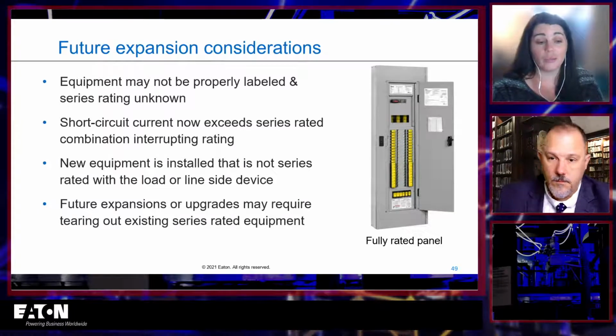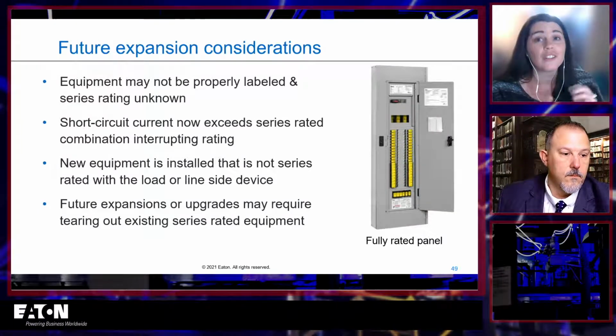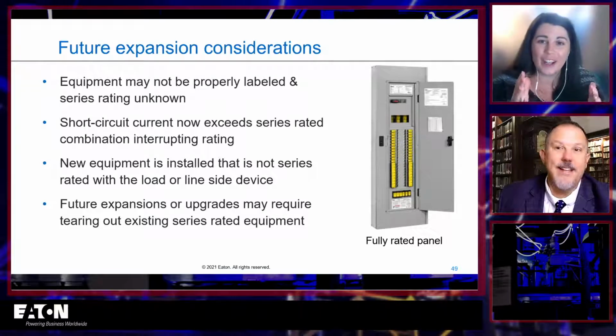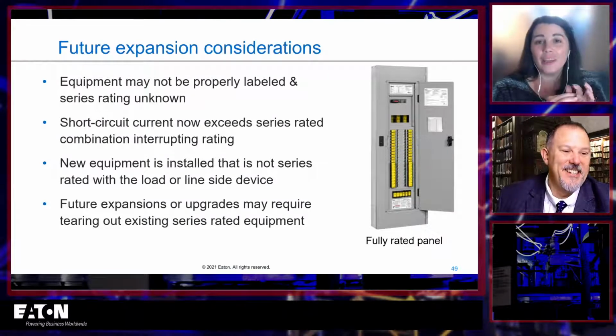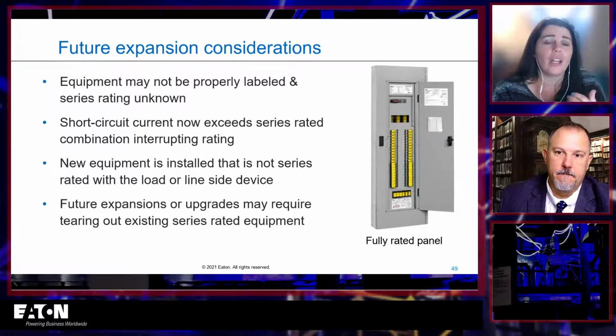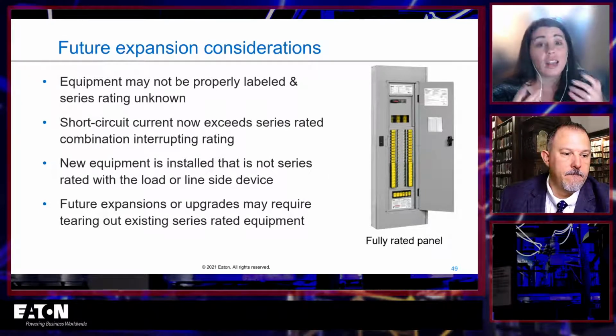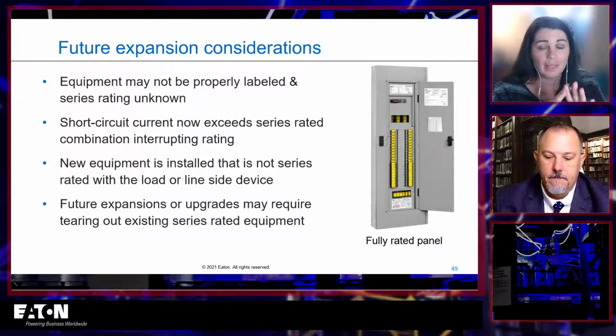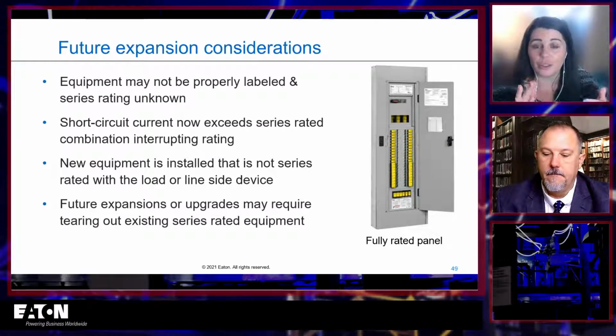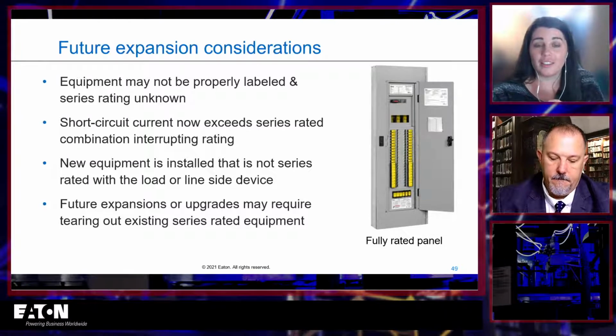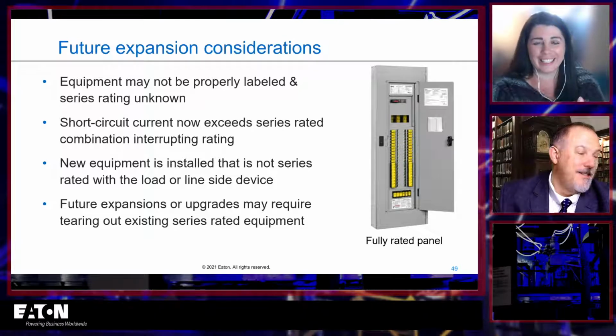So it's also the fault currents only ever get higher whenever, right? The power just gets more dense, and when power gets more dense, the fault currents go up. So when you add capacity, etc., you could have new equipment installed that doesn't have a series rating with it. It makes it a lot messier in the future too. So yeah, you just don't do series ratings unless you really, really have to.